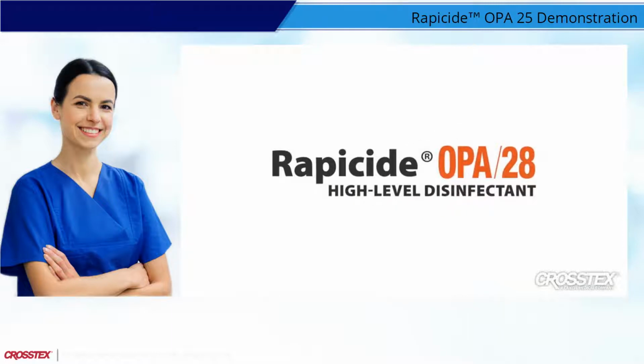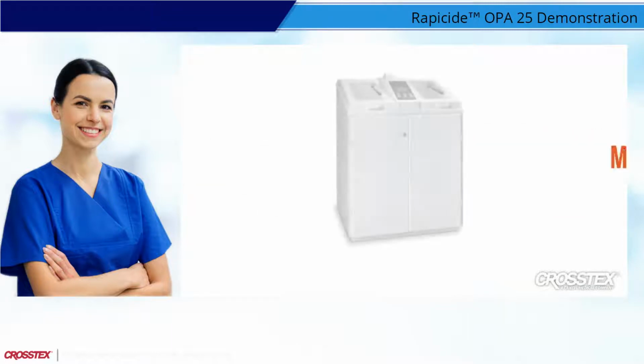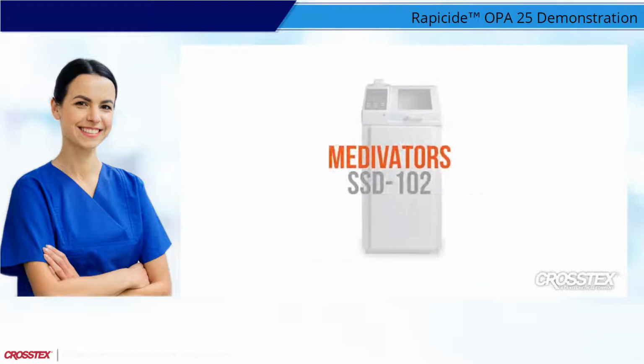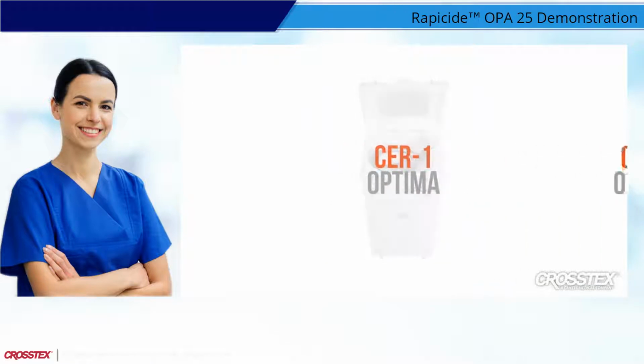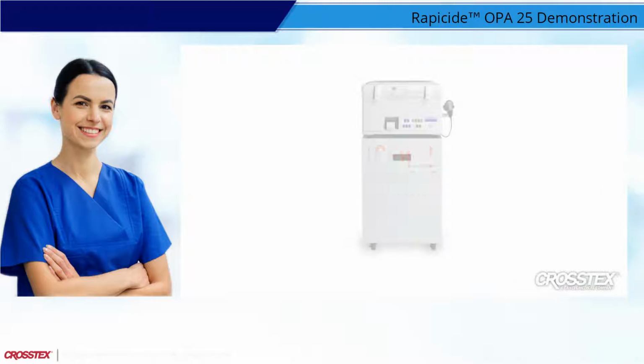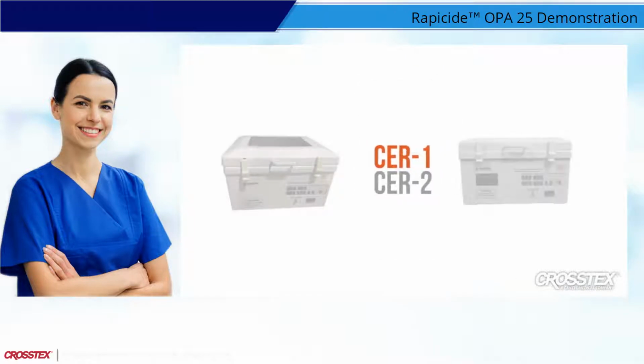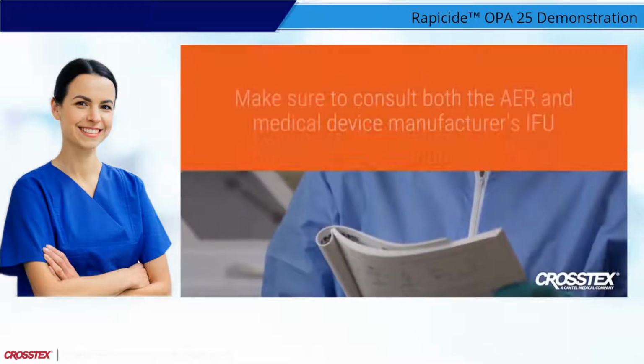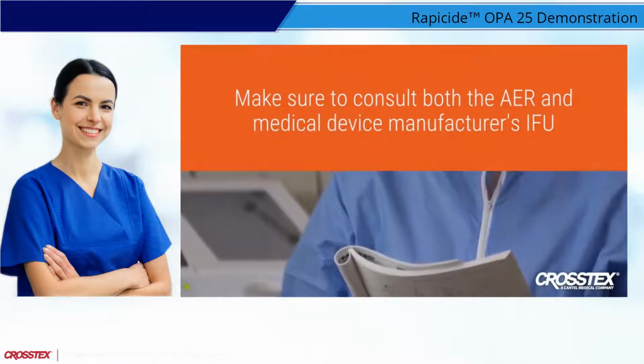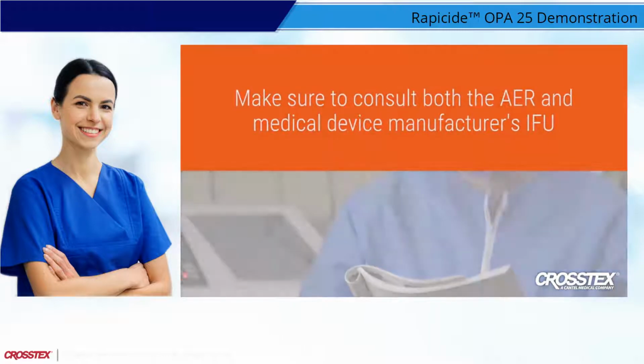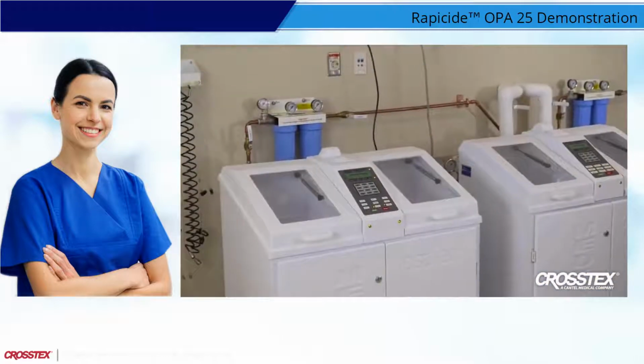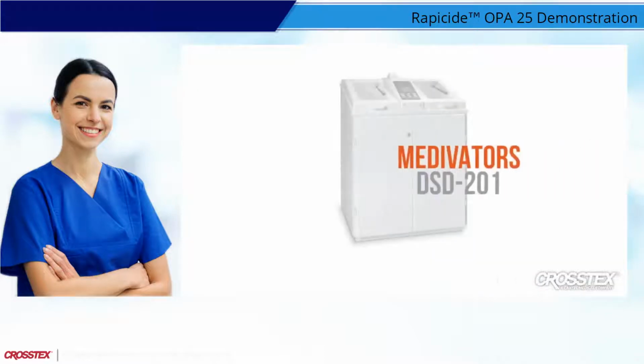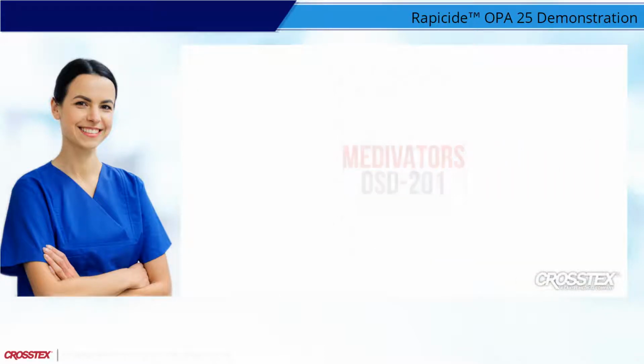Let's review the changeout and disinfection procedure for Rapicide HLD when using an AER. Rapicide OPA 25 high-level disinfectant has been validated for use in the Medivators DSD-201, SSD-102, CER1 Optima, and CER2 Optima automated reprocessors, and the CER1 and CER2. Make sure to consult both the AER and medical device manufacturer's IFU, which comes with the equipment and must be read prior to use. In this example, we will be using the Medivators DSD-201 Dual Basin AER.